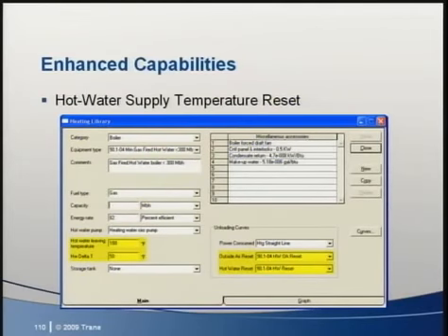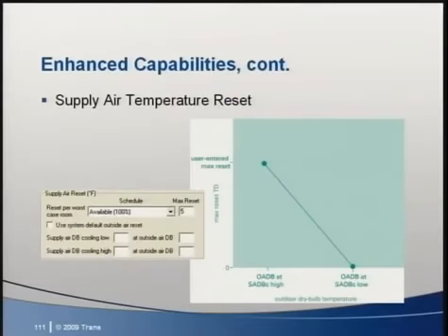Two separate unloading curves, one for the outside air reset and one for the hot water reset, work in conjunction with the entered values for hot water leaving temperature and hot water delta T, which is used to determine the hot water return temperature. Okay, now, let's talk about supply air temperature reset. Per Appendix G, the baseline supply air temperature for cooling must be reset higher by 5 degrees under the minimum cooling load conditions. In TRACE, supply air temperature can be reset based on outside air or space conditions, as well as limit the amount of reset allowed.